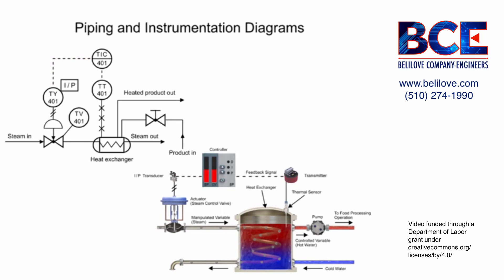The controller output is connected to the transducer that controls the steam flow, indicated by the second letter Y of the functional identifier. The transducer converts an electronic signal to a pressure signal and is indicated by the square containing the letters I and P.